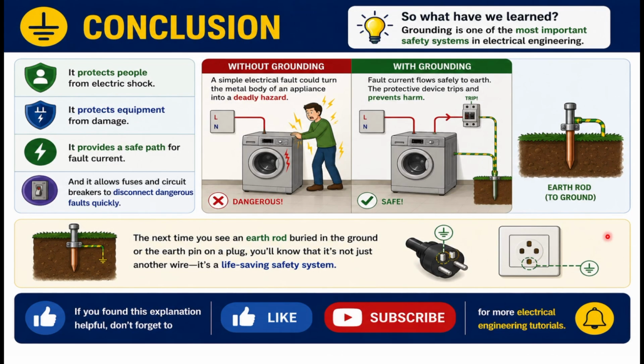And for the conclusion, it is important to note that grounding is used mainly for protection. It protects people from electric shock. It protects equipment from damage. It provides a safe path for fault current to flow to the ground, and it allows fuses and circuit breakers to disconnect dangerous faults quickly. So basically, that is it. If you have a device that is connected without earthing, in case of a failed installation, someone touches it, the person gets shocked. And with proper grounding, if there's a failed circuit, the leakage current is going to flow to the ground, leaving the circuit breaker to trip, so the fault can be fixed.